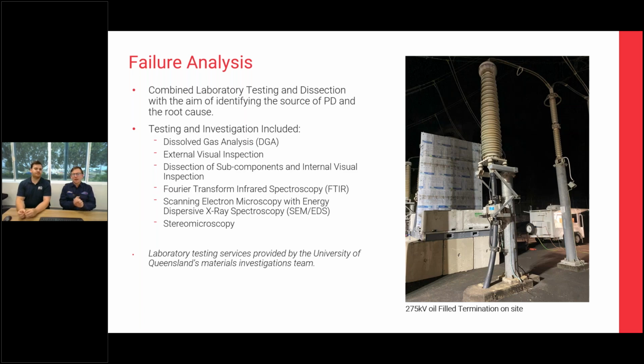So the failure analysis combined laboratory testing and the dissection with an aim to identify the source of the partial discharge inside this oil-filled termination. So this was an XLPE cable in an oil-filled termination, which was filled with a synthetic silicone oil.